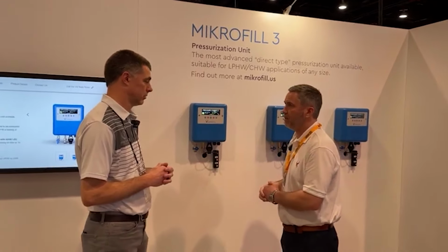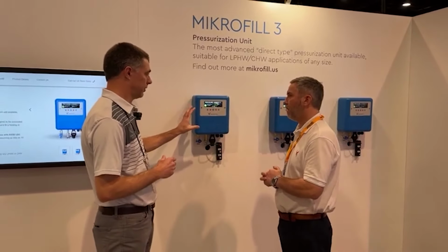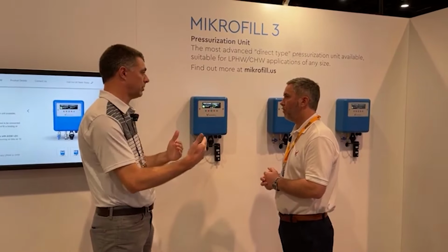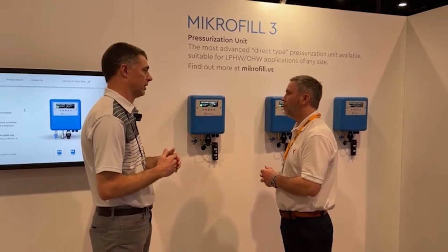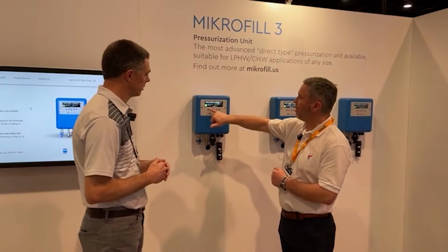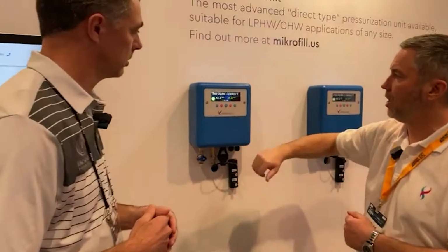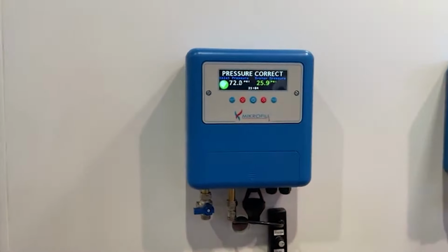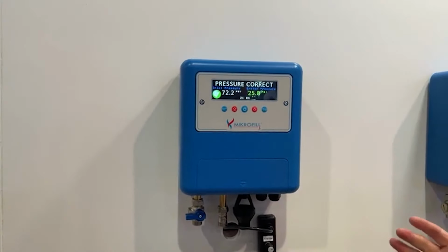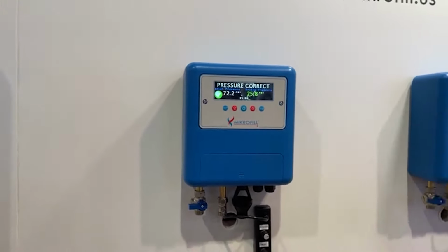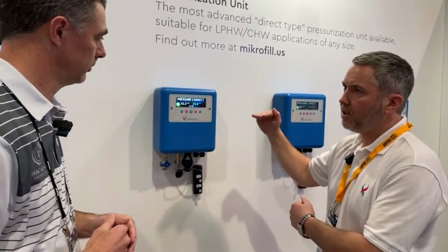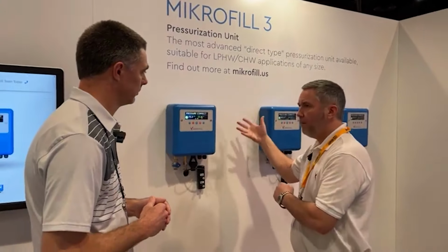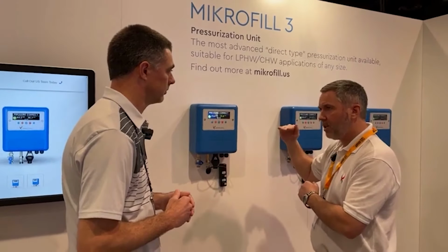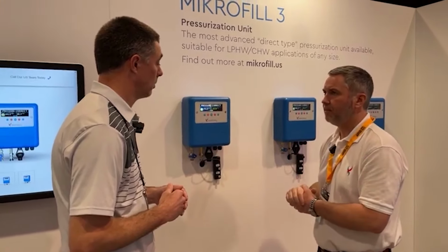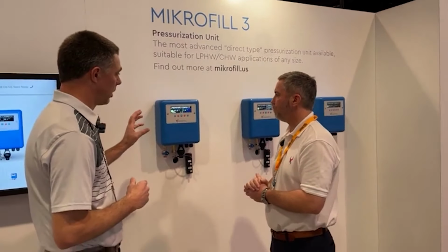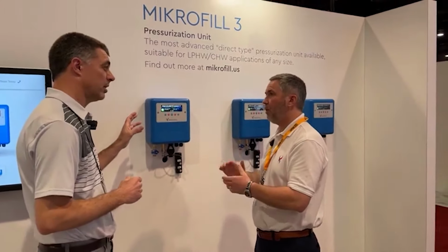Awesome. And so I'm guessing with the electronics in this, say if it needs a fill up or a top up on that system, it's going to keep track of all of that electronically. Correct, yeah. As you see on the left-hand side here, it's monitoring the incoming pressure that's constantly changing, and this is the system side, which of course changes relative to temperature. Once it's hit its target pressure, and there's maybe some nitrogen exhausted out of the system, it knows what it's trying to hit on a target cold fill. It opens up the valve, administers the relative volume of water, it hits its target, closes again, and monitors constantly. That's pretty nice. So kind of like an electronic fill valve, I would call it. That's exactly what it is, yeah, you've got it.